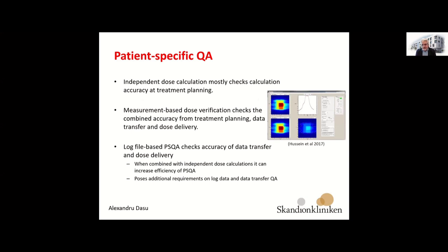Now, each of these, as I started saying, have their advantages and disadvantages. Independent dose calculation mostly checks calculation accuracy at treatment planning, and you have to complement it with a measurement of the delivered dose for the patient. And this is why measurement-based dose verification checks the accuracy both of the treatment planning data transfer, so that the right plan has arrived at the treatment machine, and the dose delivery accuracy of the treatment machine. Log file-based patient-specific QA checks the accuracy of data transfer and the dose delivery.